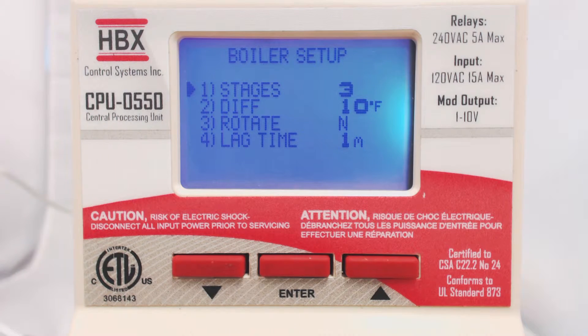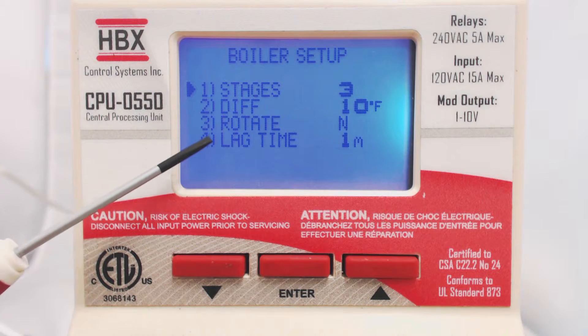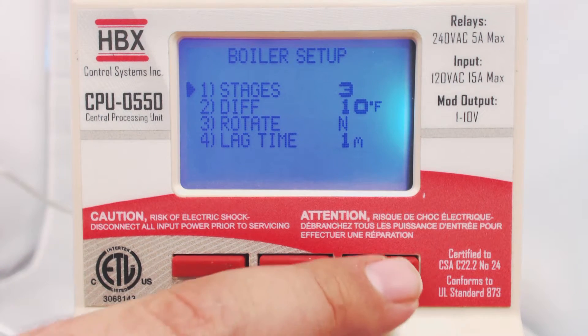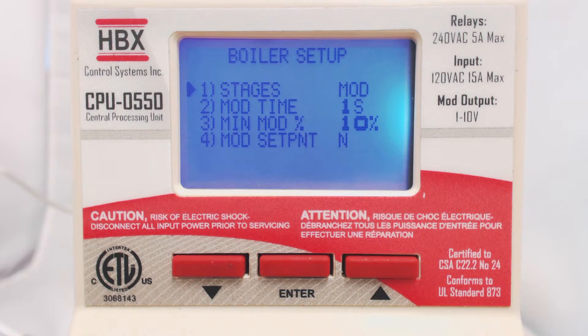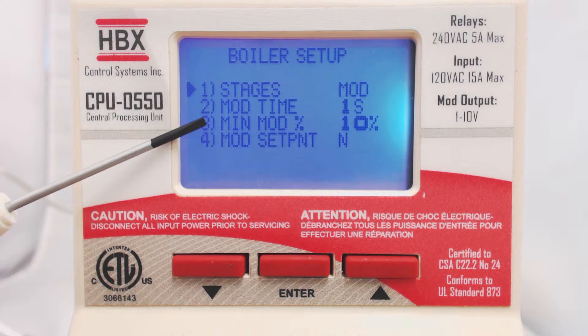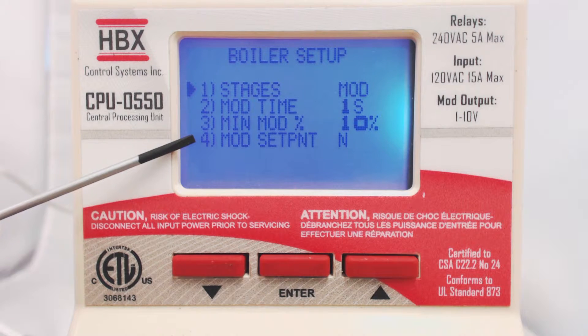With multiple stages, you can select Rotation and Lag Time. There is also a Modulating boiler option. Here you can select the time between steps and the minimum modulating percentage. If Mod Setpoint is set to Yes, the control will modulate based on output temperature and not on burner signal.